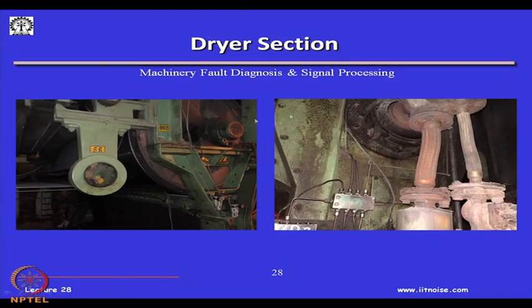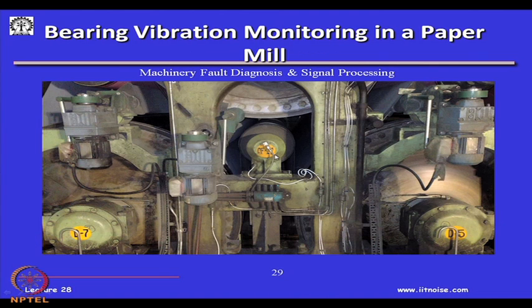After you have pressed and removed the water from the paper pulp, it has to be dried over a series of rolls. And then these are the bearings. I have another view. Every roll has a bearing. There is a bearing here, and a bearing here. And you will see that in such a plant, the bearings are monitored by vibration. You will see these white lines here. There is a bearing transducer here, another bearing transducer here, and another here. So, round the clock, vibration monitoring of these rolling bearings is being done.